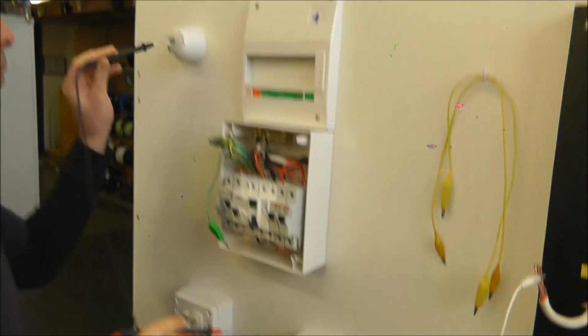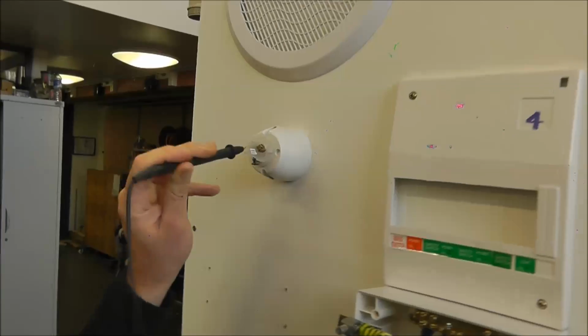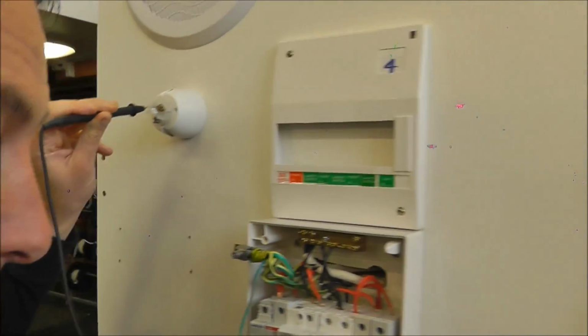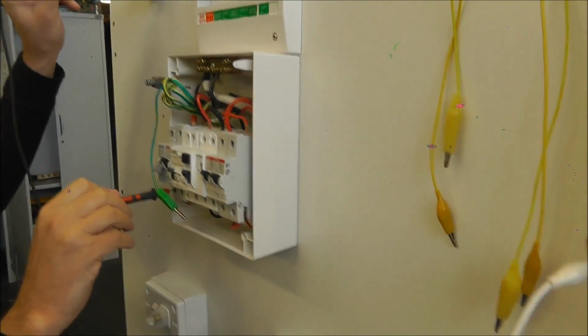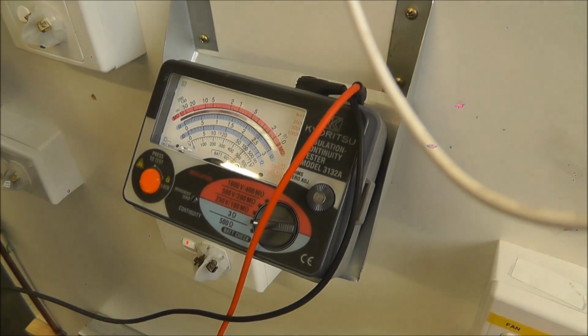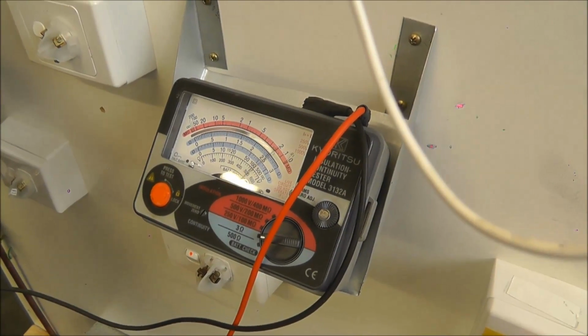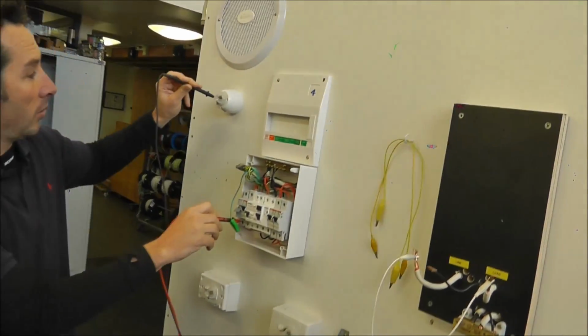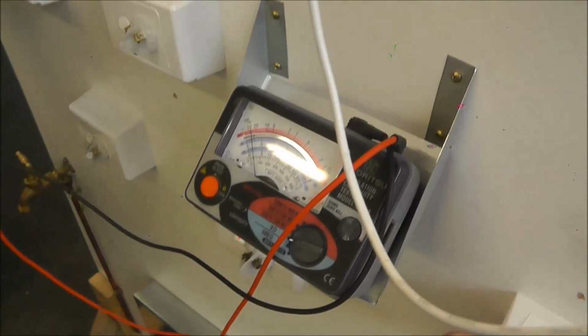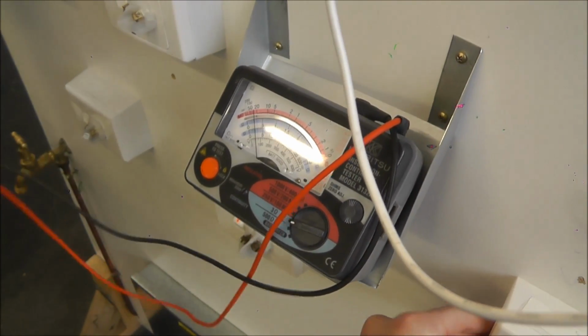And over here on the last one, I'll muck that one up later. Between active, I'll go over here. Yep, that RCD will probably go. No, it didn't. Active is switched. Okay. If I wanted to check the neutral, I'd go to the neutral terminal, to the neutral bar. Now, once you've established that one switched and not the other, then you're fine.